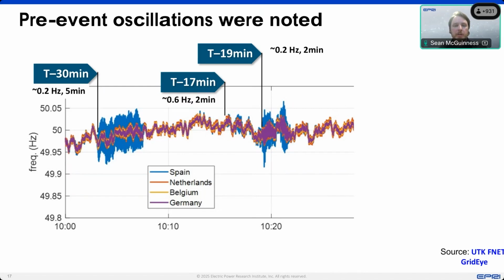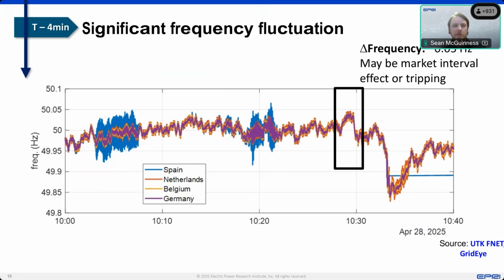So moving from the minutes then up to 4 minutes before the event began, you can see at pretty much exactly 10:30 there was a sudden drop in frequency. It was relatively small in magnitude, 0.05 hertz, 0.06 hertz. The fact that this happened at almost exactly 10:30, this is in UTC time, which is 12:30 in Spain. Because this happened at almost exactly 10:30, we do suspect that it's a market interval, so it's just some market trading. So there's a market trade that kicked in at 10:30, that changed flows, and that's why we see this sudden change in frequency. So we don't necessarily jump to the conclusion that that was a generator tripping or other event, but it may have been a tripping, but we suspect that that's a market interval.